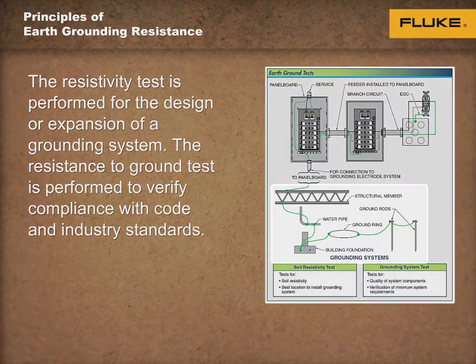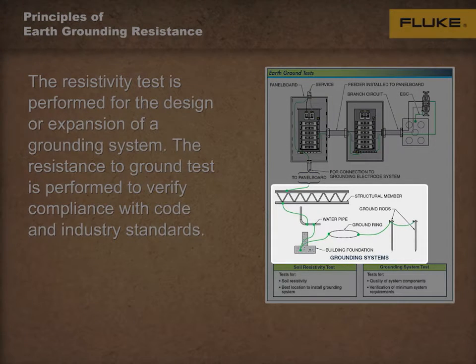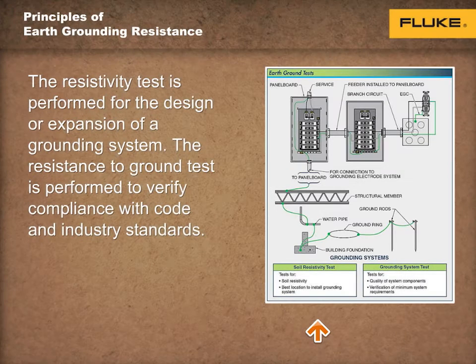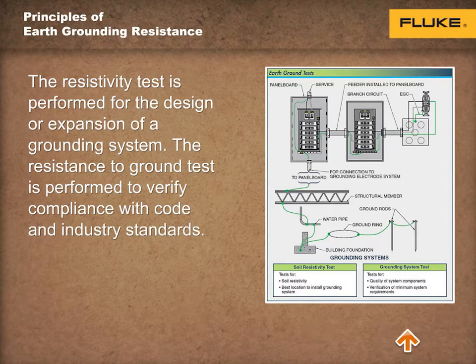The resistance to ground test is the actual testing of the grounding system components, such as the rod, the plate, the ring, etc., to verify and document that the selected grounding method and installation meets all minimum resistance requirements in ohms as required by the code and industry standards.